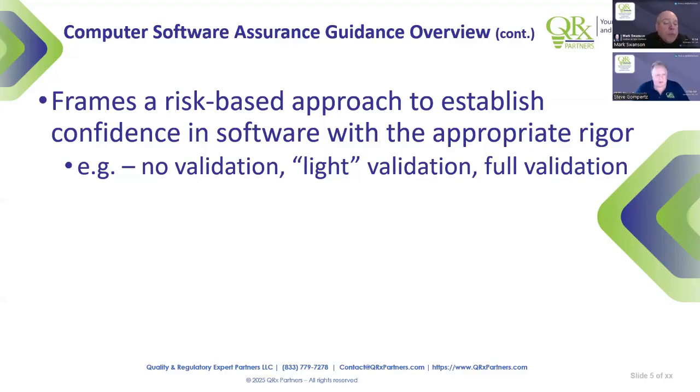And this one answers that question going, well, yeah, FDA allows you to scale that approach like it does with everything, or at least that 13485 does. So that risk-based thinking is definitely meant to be part of this. And I think that's what makes this a really valuable guidance document: it finally gives you a way to scale this, to not overdo it and not to underdo it. Because those are the two ends of the spectrum that we usually see when we're talking to our clients and doing audits and those kind of things. Either it's not done well at all, or it's just a one size fits all, and you're way over validating certain systems.